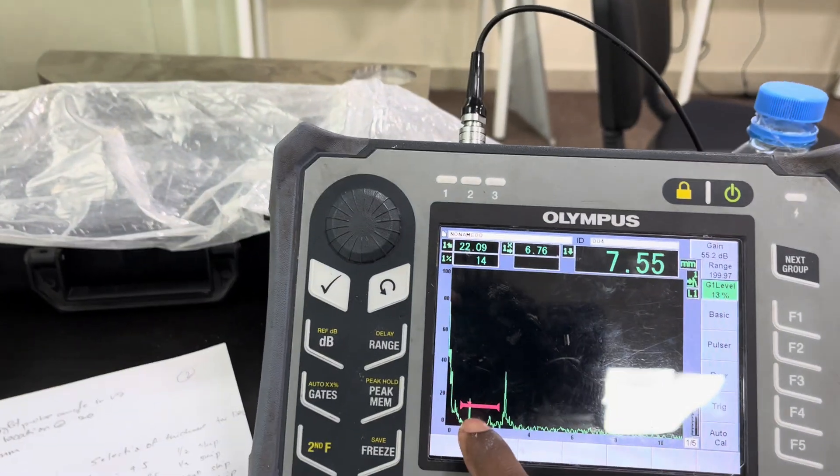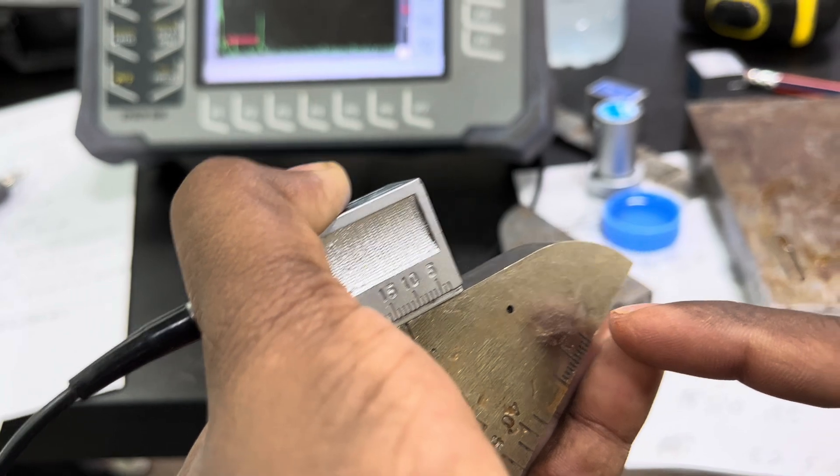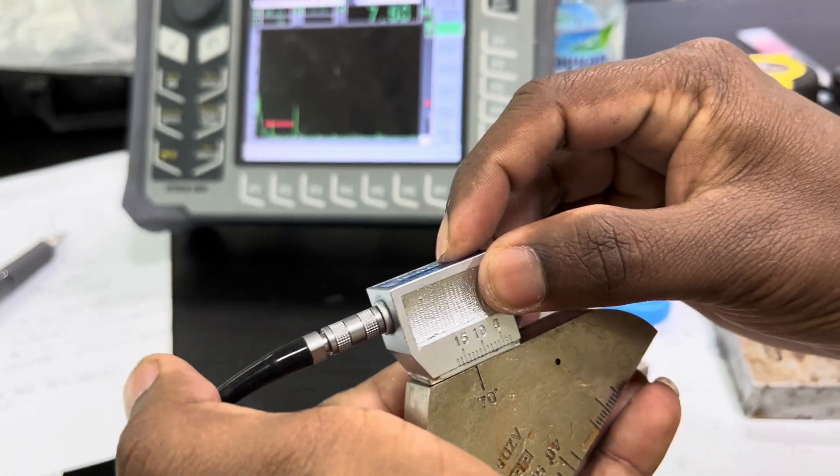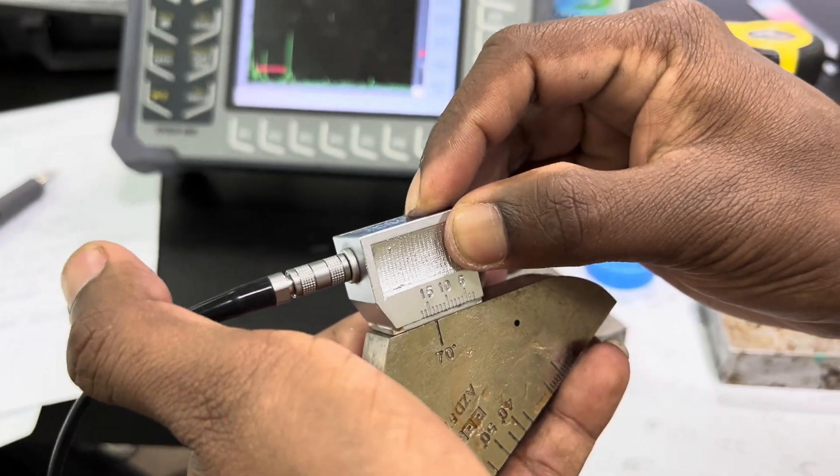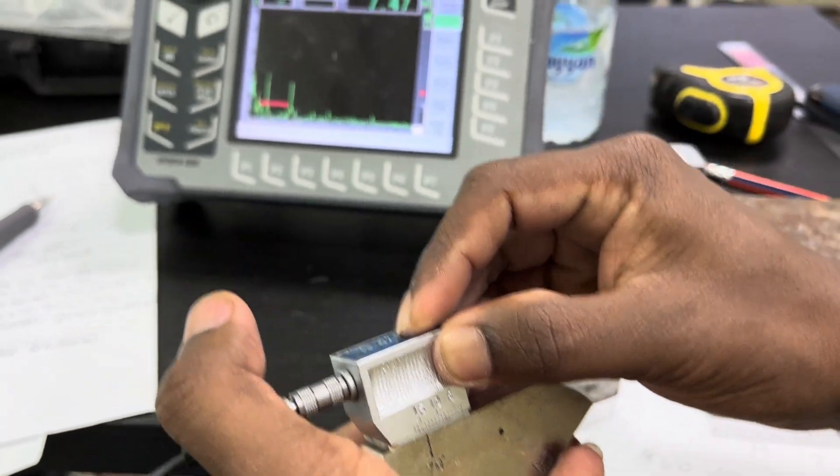This is the defect echo. It shows 7.5mm. Now the probe sensitivity is also good. The angle beam calibration is finished.